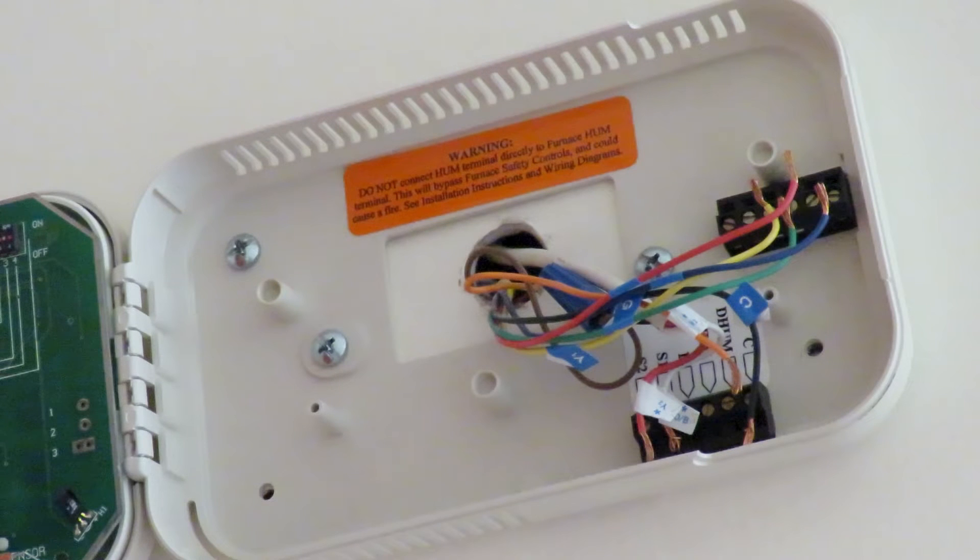So now I have to tag all my wires before I disconnect them, which I've done. I put the R tag on the red wire, the Y1 tag on the yellow wire, the G tag on the green wire, the C tag on the black wire, the W2 star tag on the orange wire, and the W1 star tag goes to the blue wire.